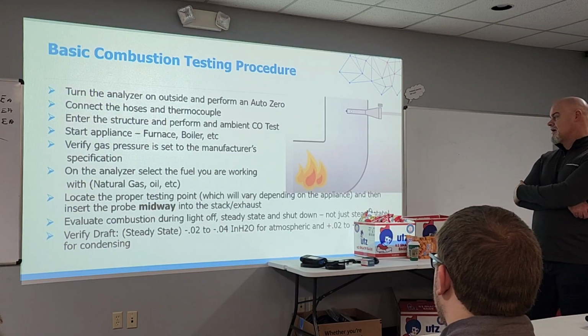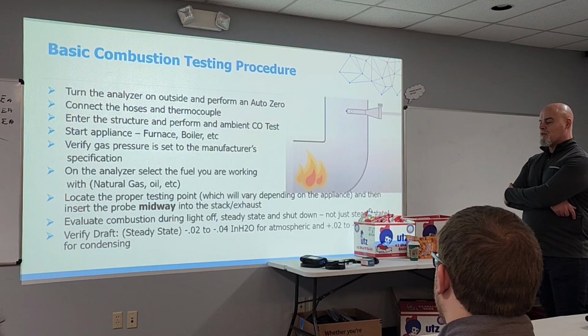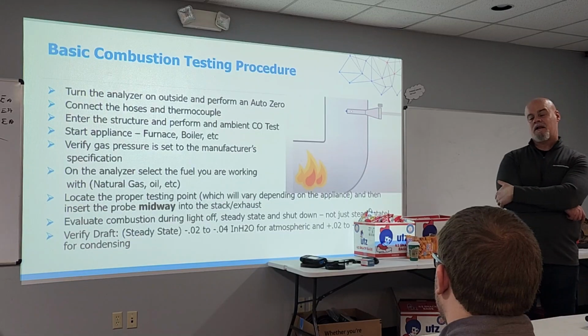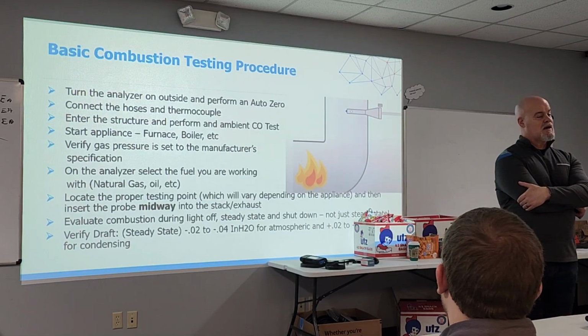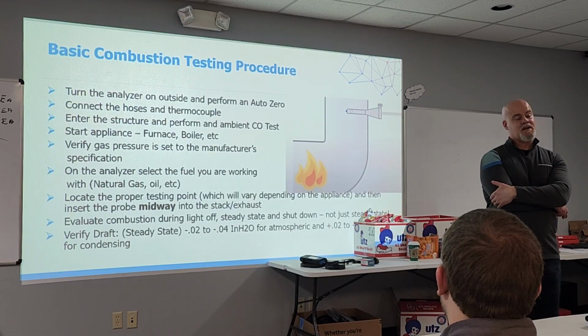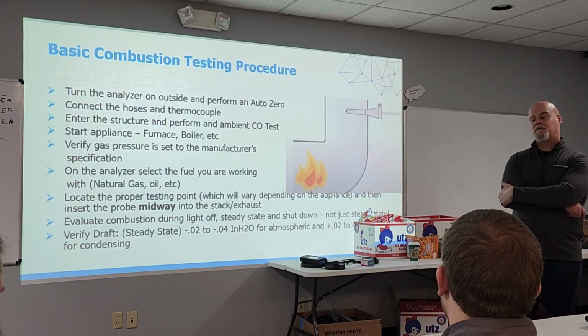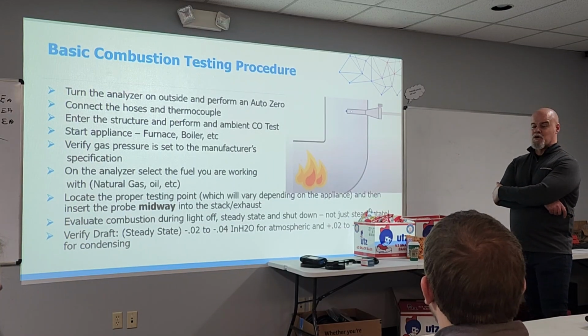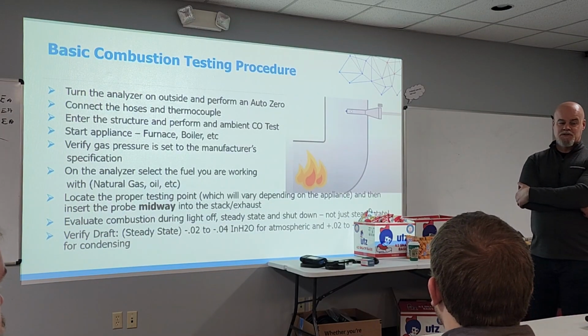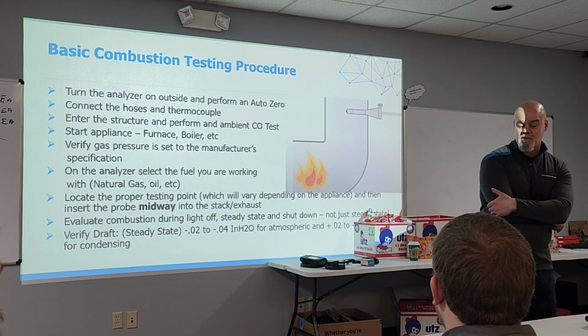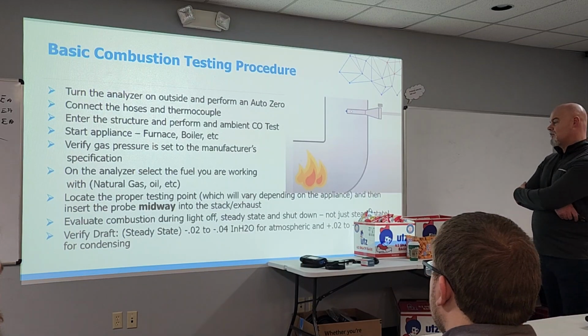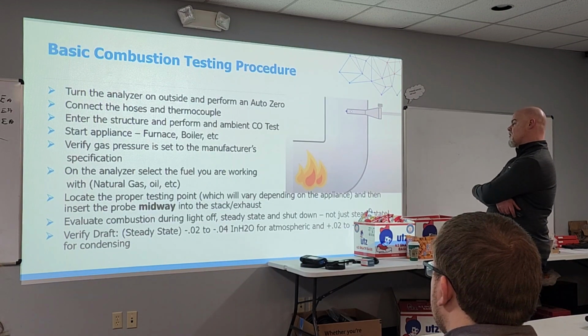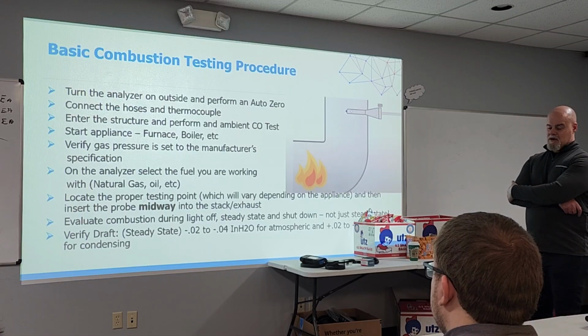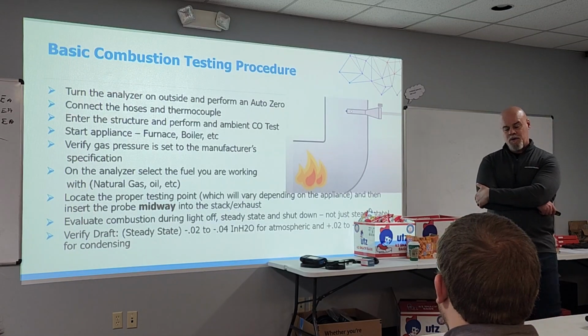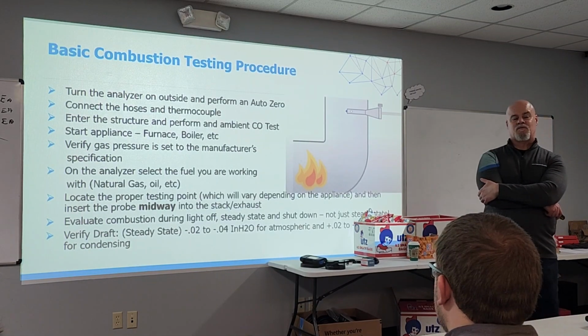But I want you testing at those different operational times because there are, again, those different diagnostic tells that will reveal themselves. So I want nothing left unfound or left as a mystery. There are no mysteries here. We are always to control these variables when we test. It is very important, okay? And you can control them. And then you're going to verify draft at steady state, which is for an atmospheric system, minus 0.02 to minus 0.04 inches of water column.